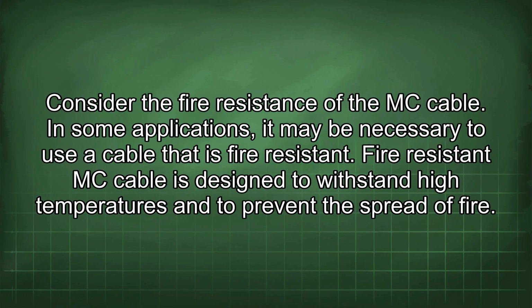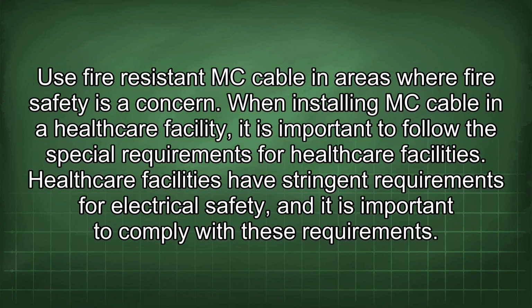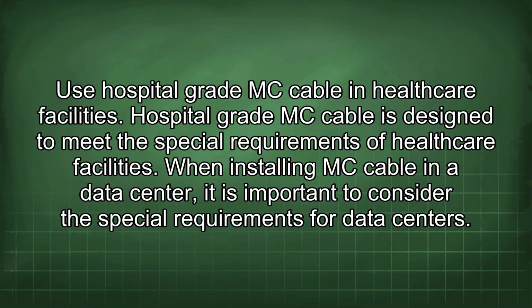Consider the fire resistance of the MC cable. In some applications, it may be necessary to use a cable that is fire resistant. Fire-resistant MC cable is designed to withstand high temperatures and to prevent the spread of fire. Use fire-resistant MC cable in areas where fire safety is a concern. When installing MC cable in a healthcare facility, it is important to follow the special requirements for healthcare facilities. Healthcare facilities have stringent requirements for electrical safety, and it is important to comply with these requirements. Use hospital-grade MC cable in healthcare facilities. Hospital-grade MC cable is designed to meet the special requirements of healthcare facilities.